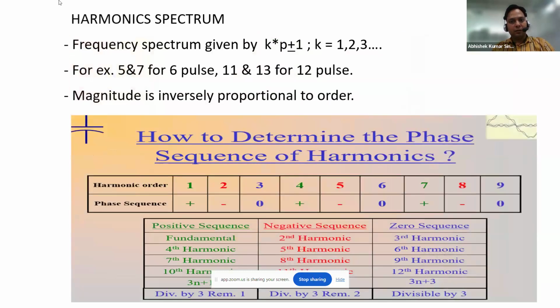Now, basically there is a formula, if you will see, K into P plus minus 1. So P is the pulse. Suppose we have a VFD. VFDs have a converter and an inverter. So a VFD will have a certain pulse number, like it can be a 6 pulse VFD, 12 pulse VFD, or 24 pulse VFD. But in industry, generally we use 6 pulse VFD. 12 pulse also we use, but the most common is the 6 pulse. So if there is a 6 pulse VFD, then which harmonic will it develop? Will it produce third, will it produce fifth, which kind of harmonic will it develop? So we'll understand from this.